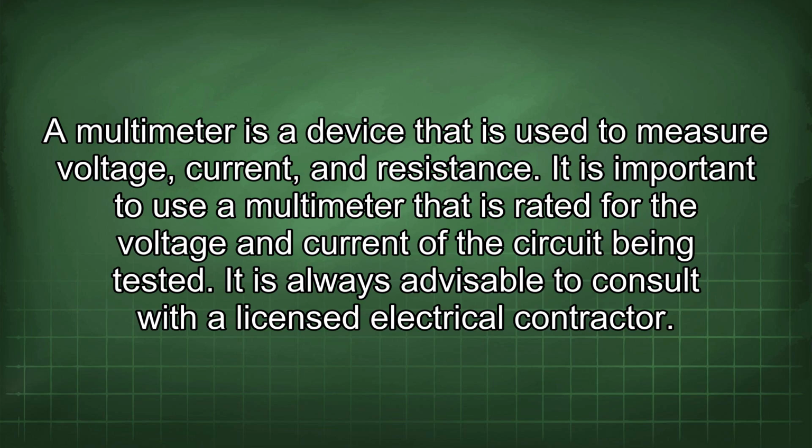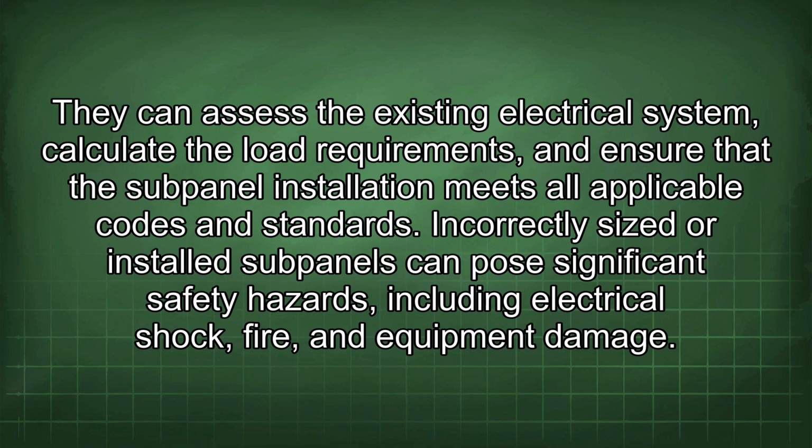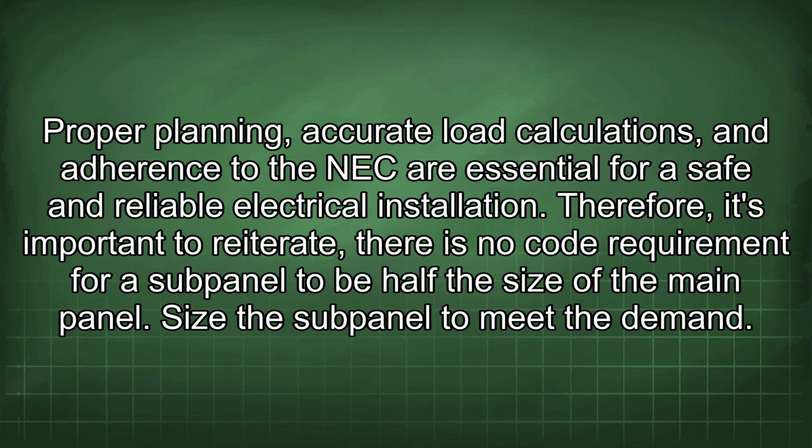It is always advisable to consult with a licensed electrical contractor. They can assess the existing electrical system, calculate the load requirements, and ensure that the subpanel installation meets all applicable codes and standards. Incorrectly sized or installed subpanels can pose significant safety hazards, including electrical shock, fire, and equipment damage. Proper planning, accurate load calculations, and adherence to the NEC are essential for a safe and reliable electrical installation. Therefore, it's important to reiterate, there is no code requirement for a subpanel to be half the size of the main panel. Size the subpanel to meet the demand.